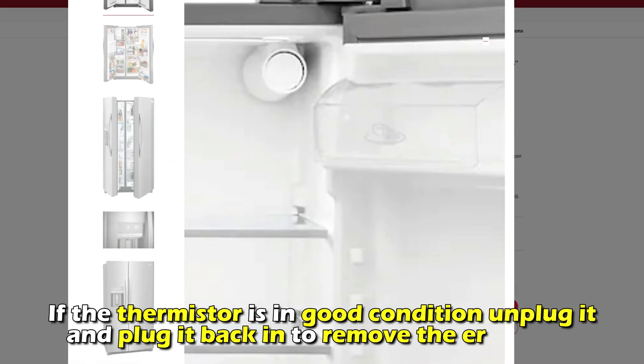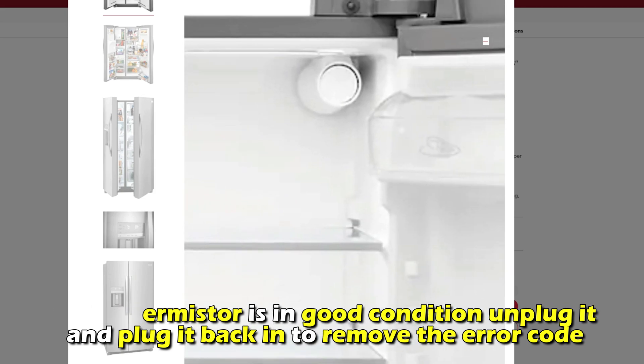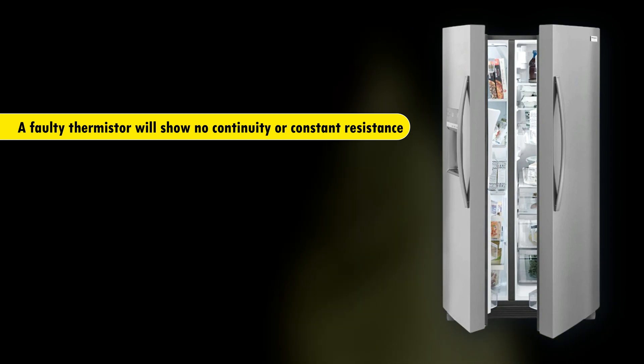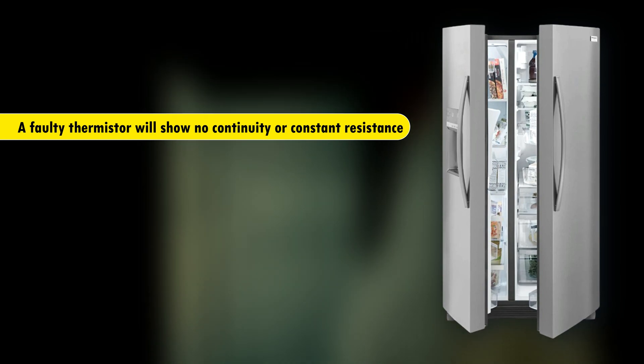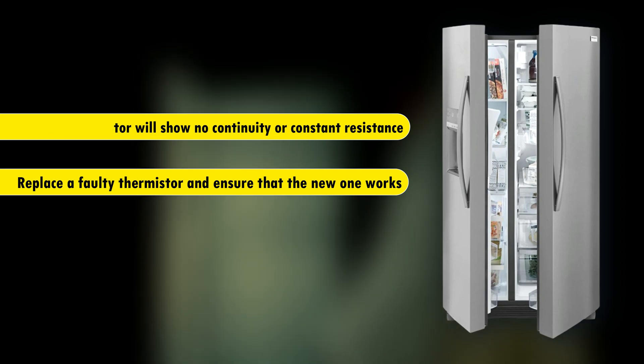If the thermistor is in good condition, unplug it and plug it back in to remove the error code. A faulty thermistor will show no continuity or constant resistance. Replace a faulty thermistor and ensure that the new one works.